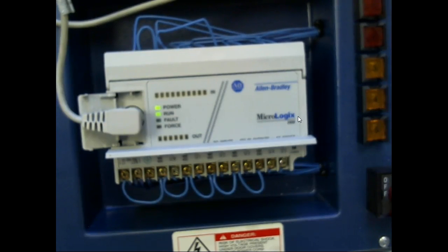So I don't know if y'all can see what they've done. So it's relay outputs. On a relay output, you can specify what type of voltage and current you need. So a relay output, that's one of the big advantages. You can use AC, you can use DC, you can have sinking or sourcing. It's up to you. So you notice what they do. Here's the hot side.